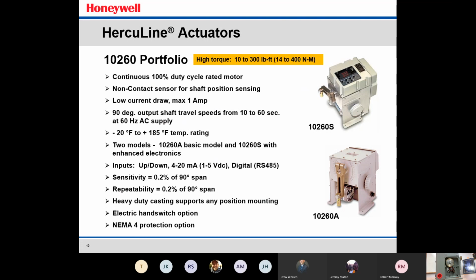The 10260 actuators, however, are rated at 100% duty cycle, and even as ambient temperatures rise in the plant around the actuator, it maintains that continuous 100% duty cycle because it does not have a braking mechanism inside the actuator. It's actually a self-locking worm gear in that actuator that's mounted right to the output shaft, which gives you high repeatability and self-locking under very high excess torque as well.